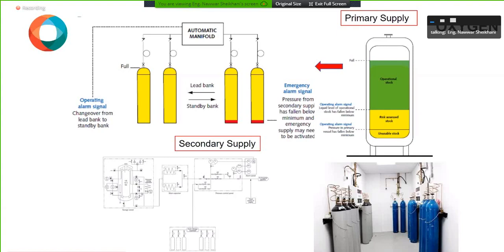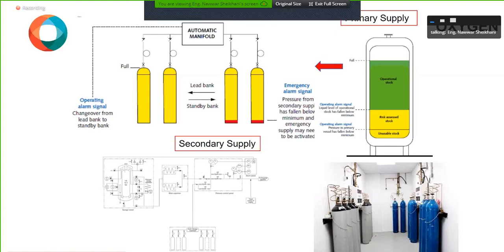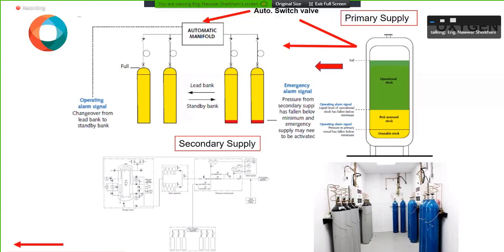However, let's come back to the secondary supply. Secondary supply means manifold. We have a right bank and a left bank. The most important item here is that we should have an automatic switch valve between the primary and the manifold. And even within the manifold, we should have an automatic switch, or automated manifold, between the right bank and the left bank. The automatic switch valve, or solenoid valve, whatever you call it.